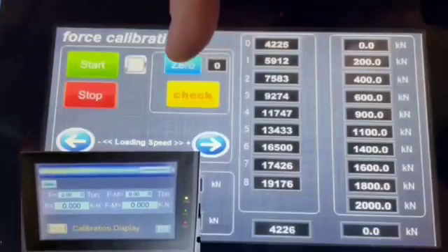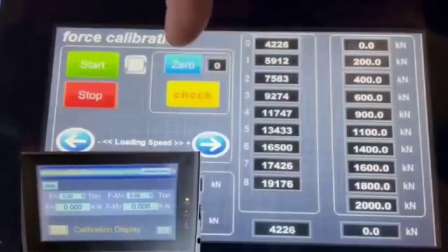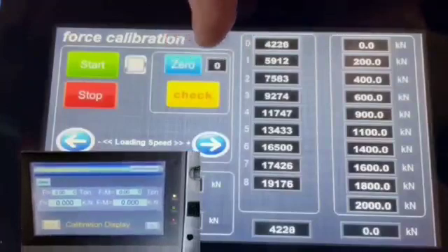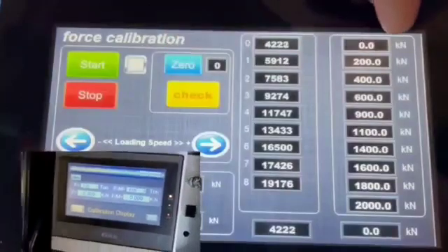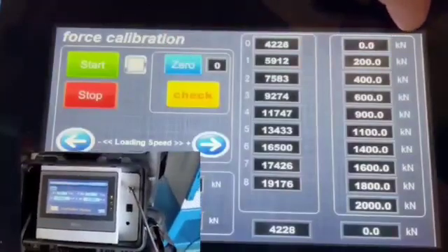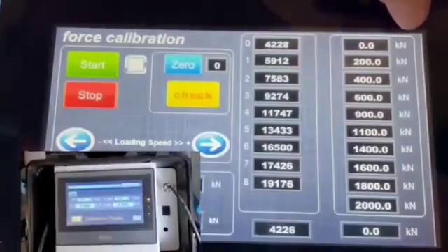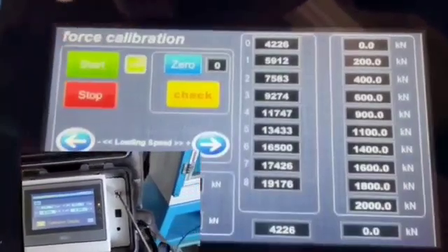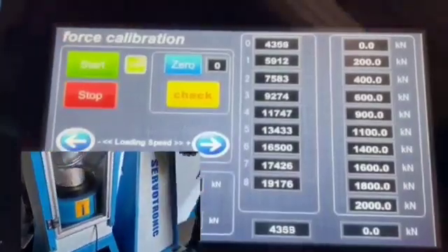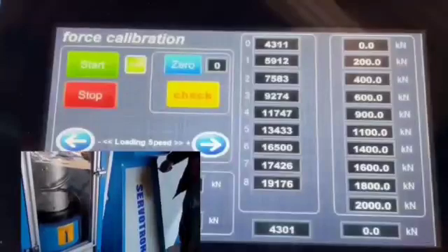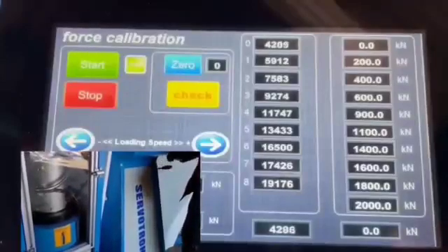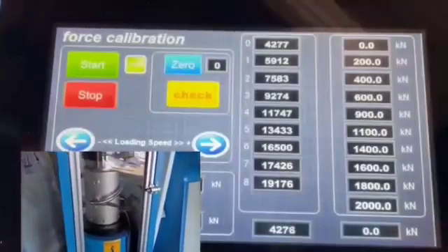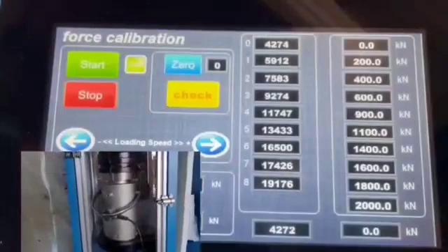When we start, after pushing the zero, we put the first check, which means we set the existing pressure on the load cell - the actual pressure for the first point. Now I hit the start and the light gets green.